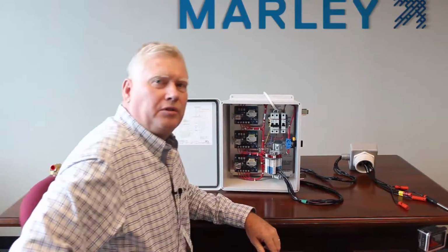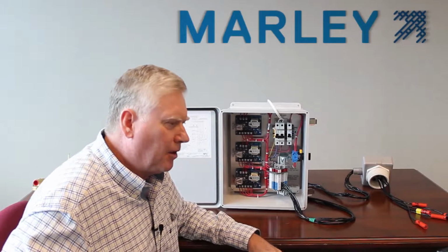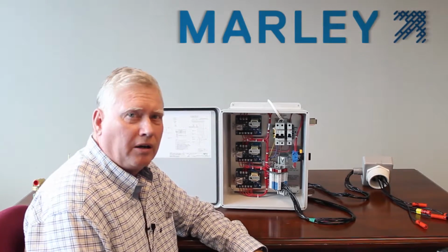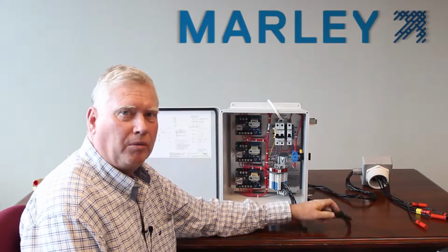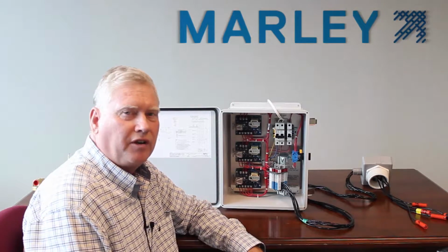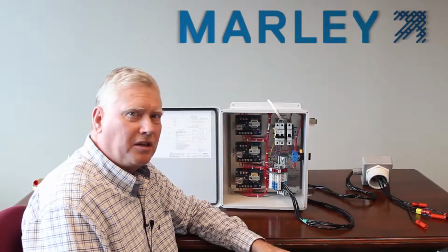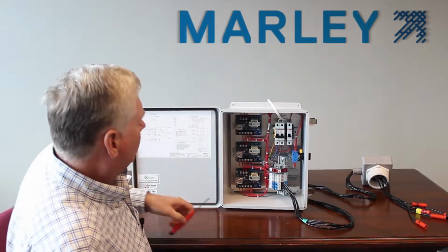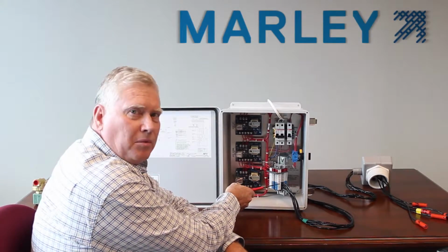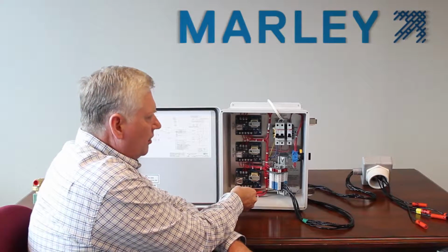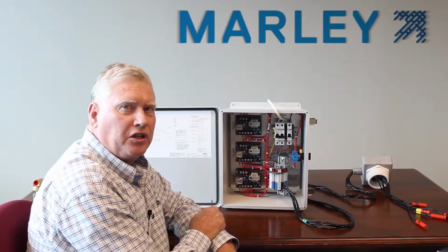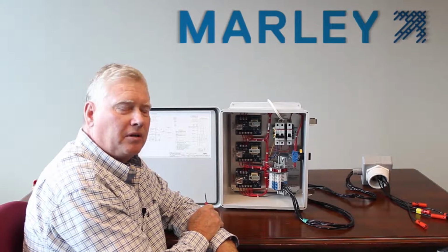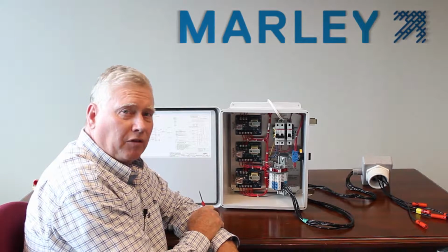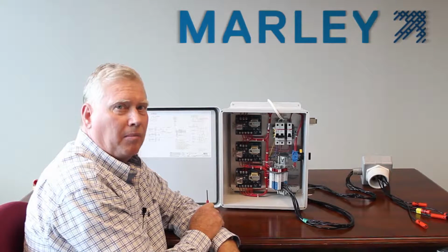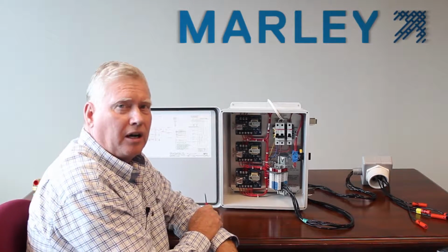Okay, let's talk about how to troubleshoot this panel. I want to start off by saying that the control panel and the water level probes that come with the panel are 100% tested at the factory before we ship them. So the panel gets assembled in the shop, and then they tie in a simulator to all these points right here, and they manually simulate water level changing up and down to prove that the panel works before we ship it. So most of the calls that we get back from the field aren't that the panel isn't working properly, it's just that it's not working and they don't know why.